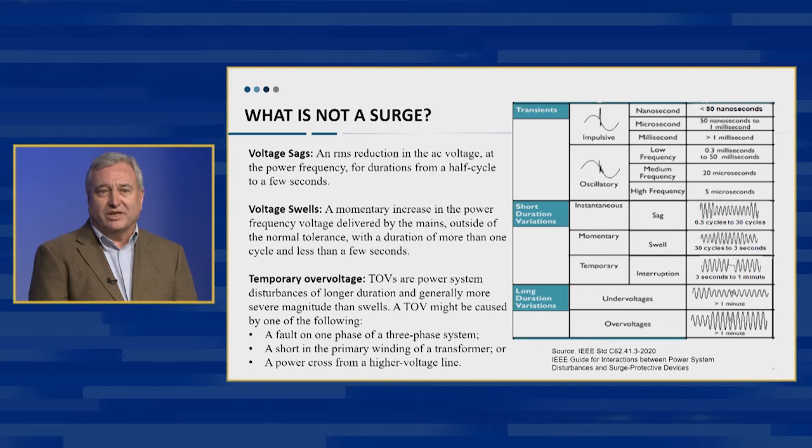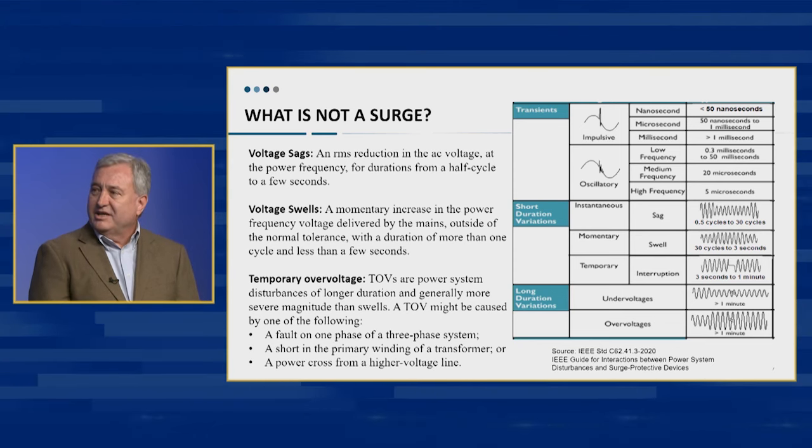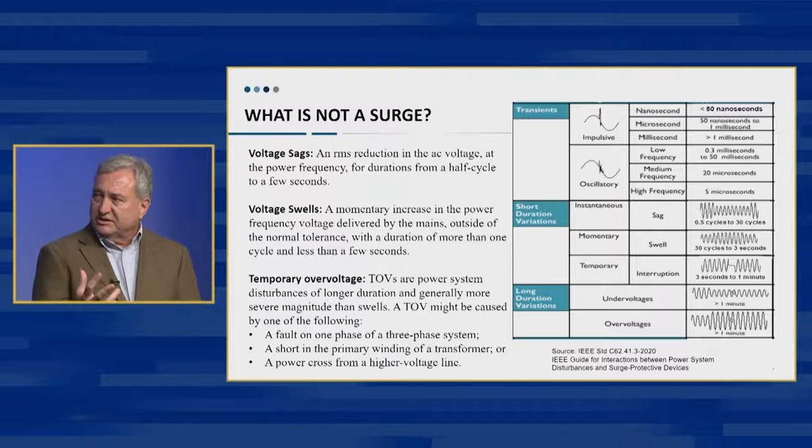So in other words, the whole function of the SPD is to go from a very, very high resistance state, almost an open circuit, it's invisible under normal situations. When it sees that transient, the resistance drops incredibly fast and creates that low resistance path, the least resistance path to ground, diverted away from the electronic equipment. And when we see these occurrences of overvoltages, the SPDs have to be designed to be able to tolerate that and not go into a catastrophic failure mode.